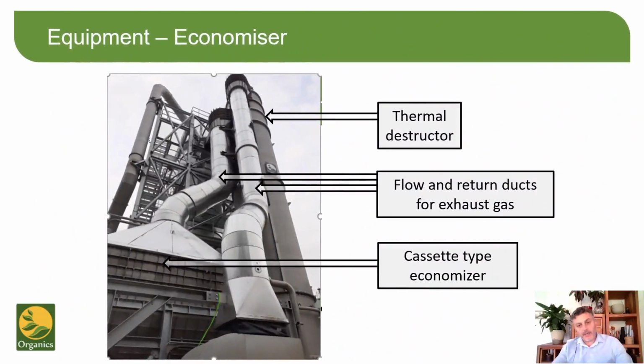The main heat input to our system is from the thermal oxidizer via our waste heat economiser. The economiser is exposed to temperatures of up to 750 degrees centigrade and has a 10-bar water circuit flowing through it. Its design and specification is therefore of critical importance. We design our own economisers based on our 20 years of experience running them on dirty gas streams. Economisers are basically shell and tube heat exchangers where the hot gases go through the shell and the water goes through the tubes. The most efficient economisers use finned tubes, but we have found that these tend to block quickly, so we've developed finless economisers that are built in cassettes that allow the economisers to be reconditioned every 5 years or so, returning them to approaching as new condition.